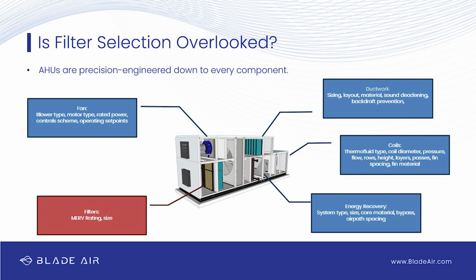The fan has different blower types and motor types — synchronous, VFD, ECM, brushless, whatever — many different kinds, each with its own intricacies. The control scheme and operating set points all change the performance of your air handling unit. The ductwork has to be precision sized, even simulated in complex scenarios to make sure it works as designed. Your coils require changes to piping diameter, fin type and spacing, number of rows, even the piping layout through the coil, to get the best performance. And if you've seen an energy recovery core, which recovers some of the air from your exhausted airstream, there are many different factors there too — system type, core material, bypass.